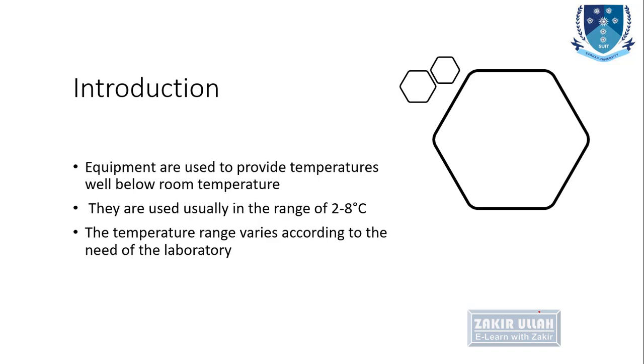For example, in certain labs the temperature may be above 8 degrees centigrade, or 10 or 15 degrees centigrade, or in some labs the temperature may be below 0, minus degrees centigrade or freezing. So usually cold incubators work below the outer atmospheric or below room temperature.